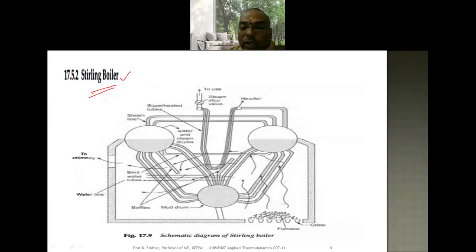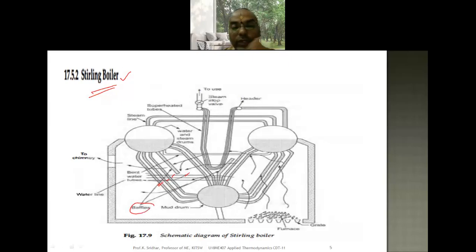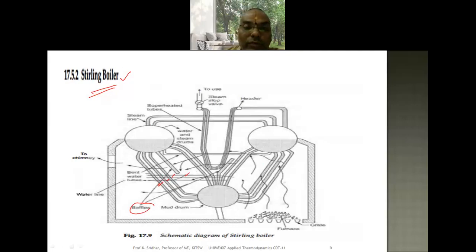Now let us look at the Stirling boiler, which is also a water tube boiler. Here we have bent water tubes, unlike the inclined straight tubes of the Babcock and Wilcox boiler. The same working principle applies. Baffles are attached to increase the surface area and improve the heat transfer rate. There is a steam line and superheater tubes similar to the Babcock and Wilcox boiler, and the steam enters the superheater tubes and leaves as superheated steam.